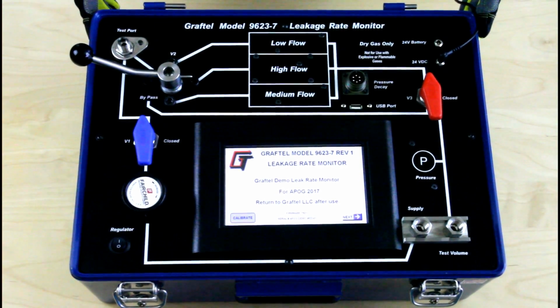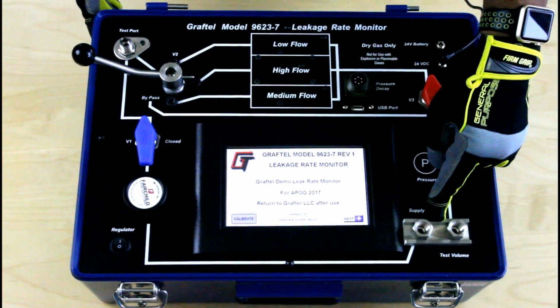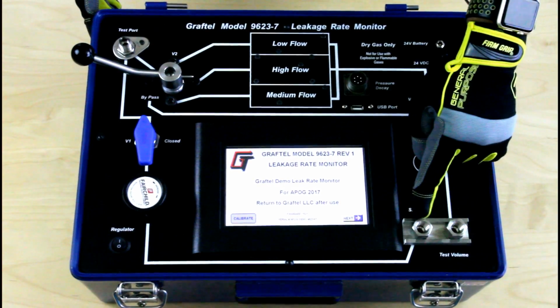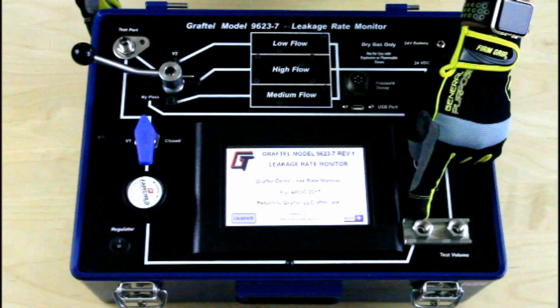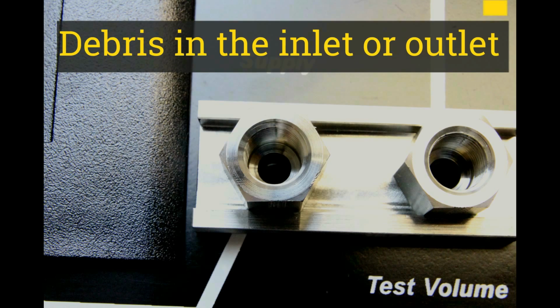Once the machine has powered up, it is recommended to perform a visual inspection of the exterior components, starting with the supply and test ports, looking for signs of blockage or moisture.